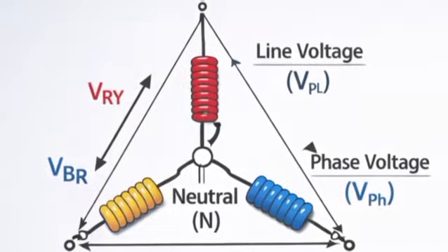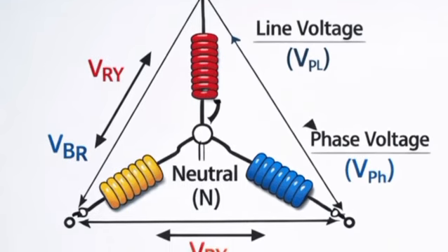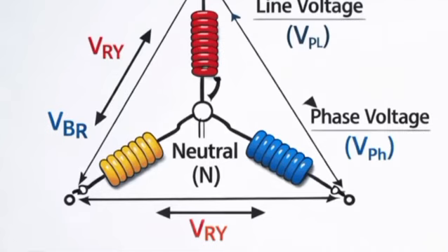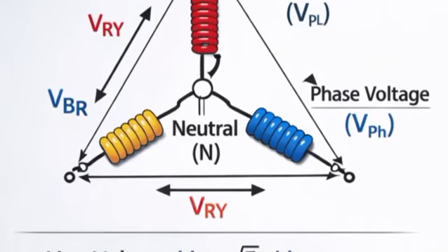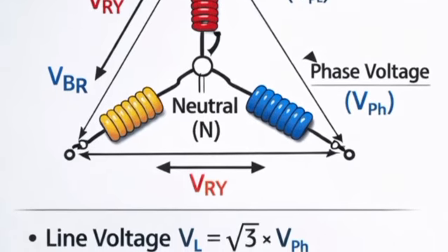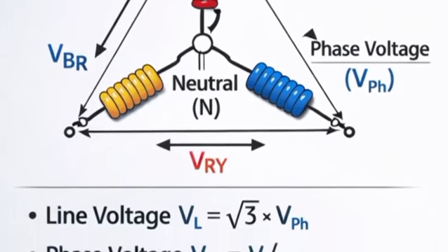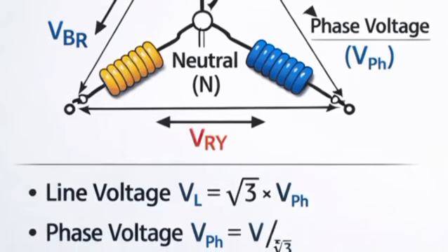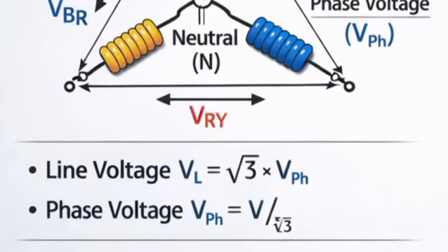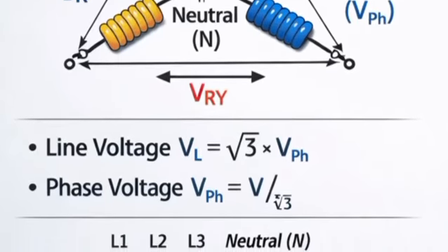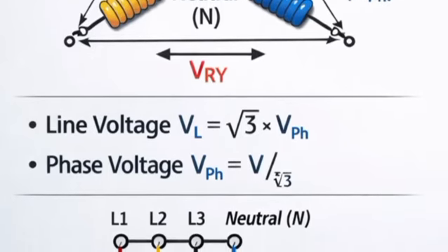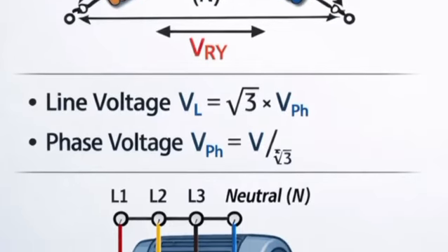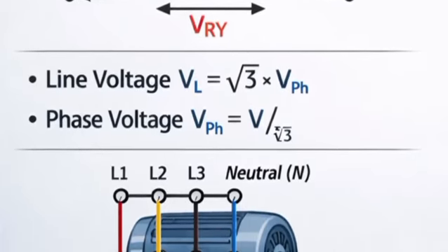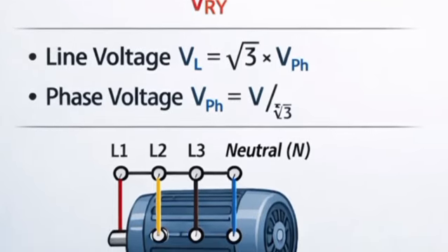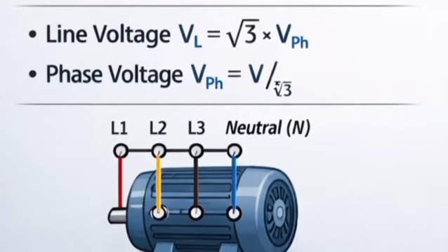Star starting stage. At start, the motor windings connect in a star configuration. This reduces voltage across each winding to approximately 58% of the supply voltage. Lower voltage means lower current draw. This stage explains the early phase of how does a star delta starter work. Reduced current minimizes electrical stress. Because star mode provides only about 33% of the motor's rated torque, the starting torque is very low, which is a limitation and not a protective feature, meaning some loads may not start under star connection.